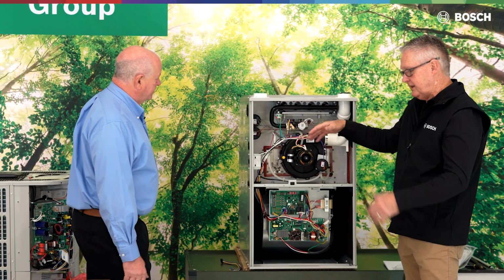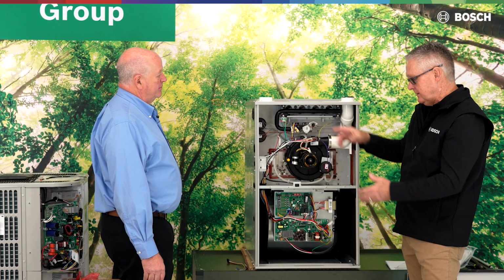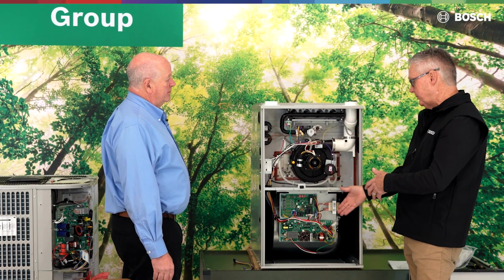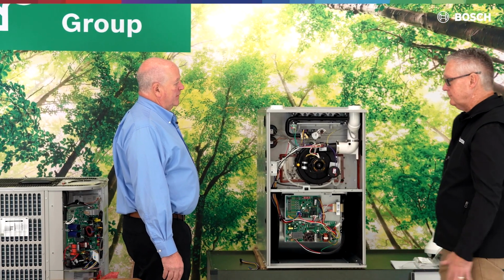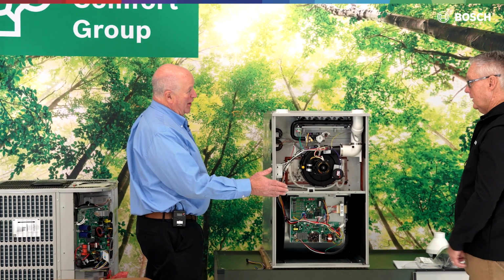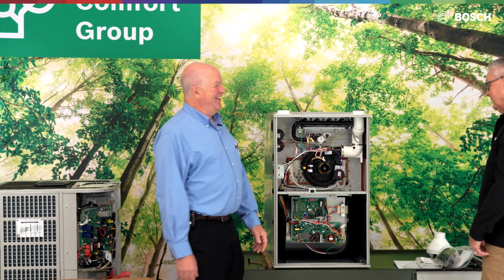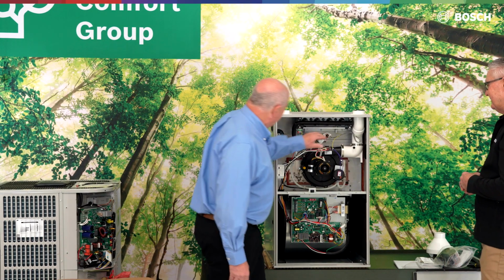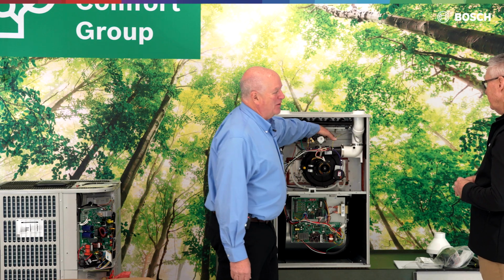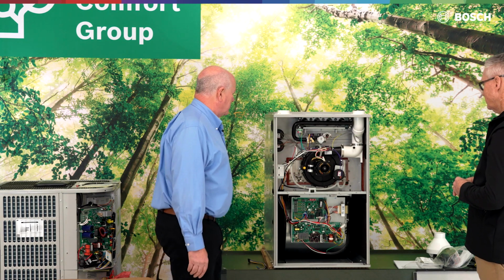And the rollout switch, the safety, has closed the circuit for the fan, and here we are. Yeah, if she knows that, I want to hire her for an employee. Exactly. She knows really well, doesn't she? Absolutely. The high limit in here is auto reset. Yep. So just the flame rollout is manual reset.